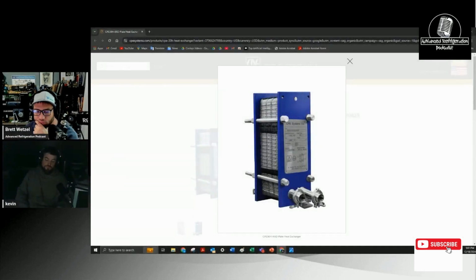This is a way better setup for 2 reasons. Because it separates all the units and equipment in the building from the actual tower water. So you aren't plugging up strainers all the time or fouling out heat exchangers or having all those issues. You just foul out the heat exchanger up in the mechanical room, and it's a lot easier to maintain because now you're only doing 1 or 2 strainers, and they can constantly do them. So that's a brazed plate heat exchanger. See how the ribs?